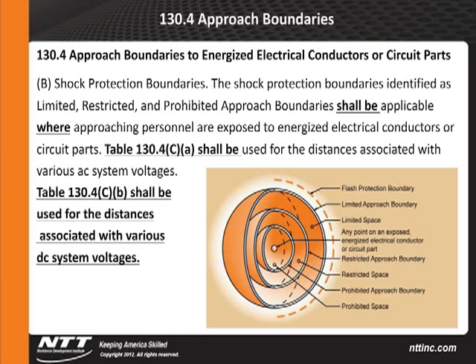Approach boundaries. So what is this thing called shock boundary? The shock protection boundary identified as limited, restricted, and prohibited approach boundaries shall be applicable where approaching personnel are exposed to energized electrical conductors or circuit parts. Table 130.4(C)(a) shall be used for the distances associated with various AC systems, and Table 130.4(C)(b) shall be used for distances associated with various DC systems. In the past, if we hadn't done an arc flash boundary analysis for systems of 600 volts or less, the arc flash boundary was 4 feet. We now have different tables for different applications, and that needs to be implemented because it could be something like 18 inches. It might be something significantly more.